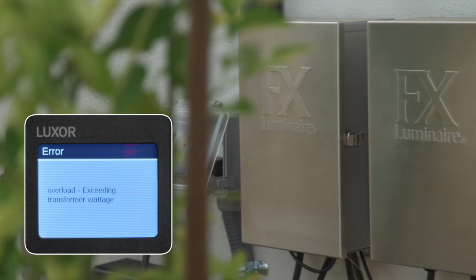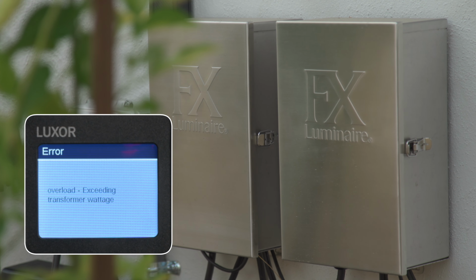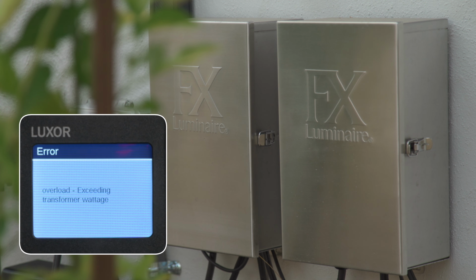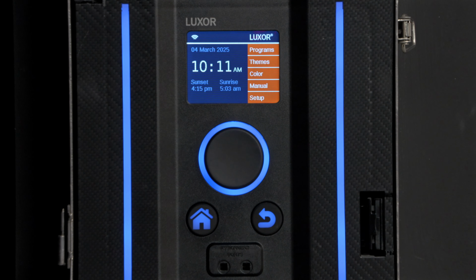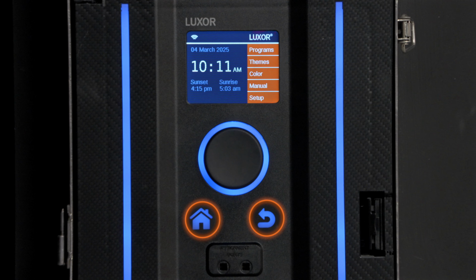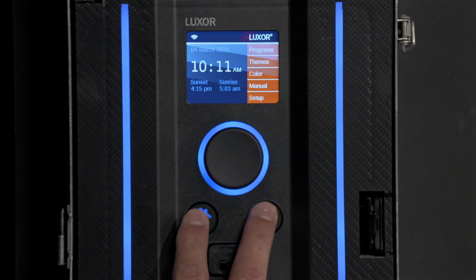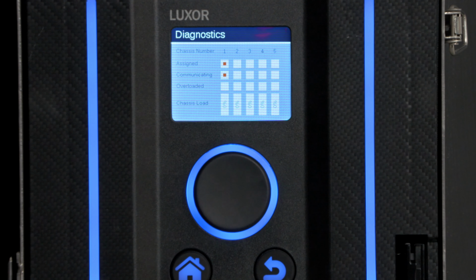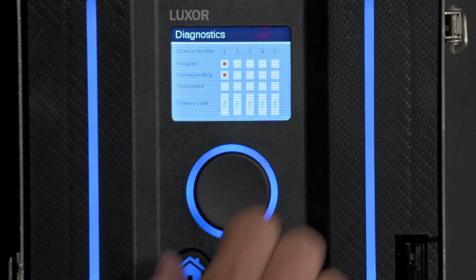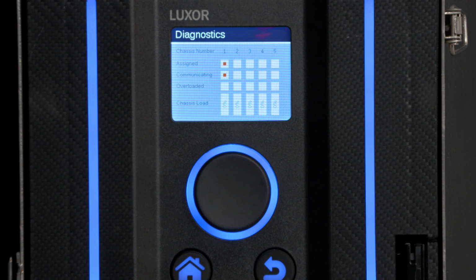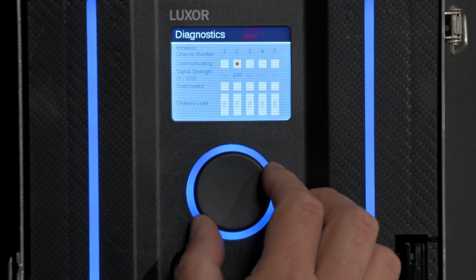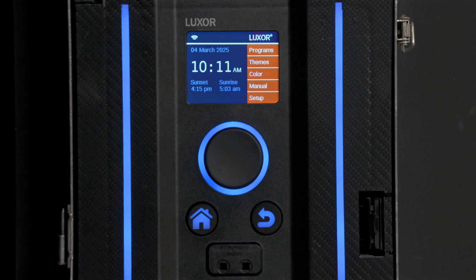Overload wattage is when there are too many fixtures on the system. The easiest way to determine how many fixtures or load is on the system is from the activity screen or the diagnostic screen. To enter the diagnostic screen, press the home and back buttons simultaneously on the facepack. Here, you'll see the different chassis installed on the system. If you have a linking system with link mods, then you'll scroll over to the right and see the same information for wireless controllers. When the system is on, it'll automatically display the activity screen.